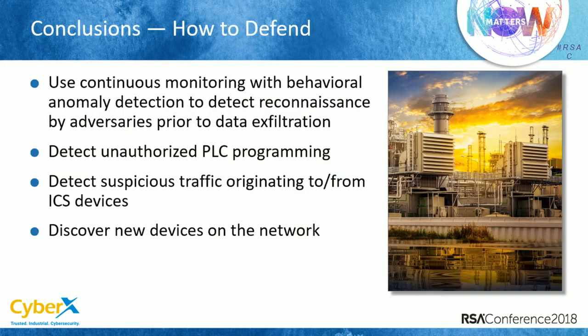A few more things: how would we defend against it? We'd want to put something in the network that continuously monitors it, looking for devices that are being programmed without the user or technician knowing, devices that start scanning the network — for example, a PLC doing a ping sweep is uncommon in these networks and shouldn't happen — and of course, new devices that shouldn't be there. Continuous monitoring of industrial networks would be the easiest and best way to address it.